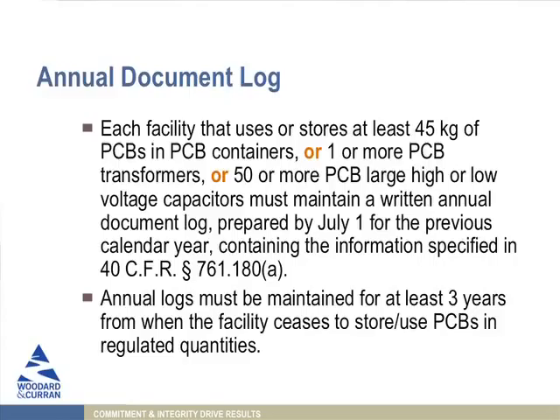If you meet this threshold, you want to keep this log. You don't have to send it to the EPA, but if they or your auditors come to inspect, you need to be able to produce it. When I spoke to Region 4, they said this is really written with industry in mind, and the inspector I spoke with said he wouldn't look for this on a college campus. However, this is officially what the regulations call for, and when I spoke to EPA inspectors in two other regions, they said yes, they would look for it. So be aware this is officially the requirement, and you must keep the log for at least 3 years.